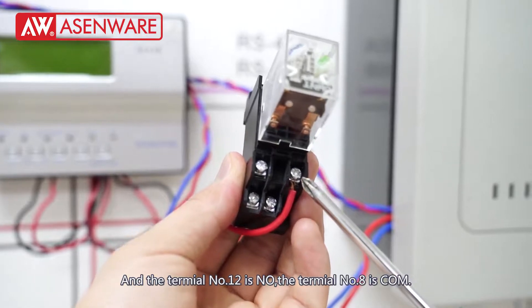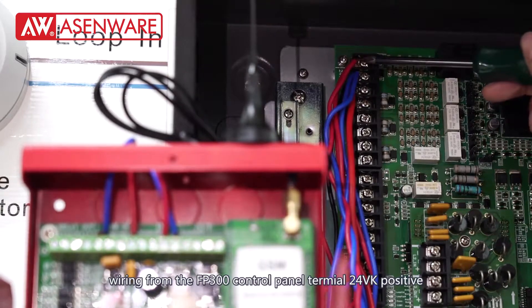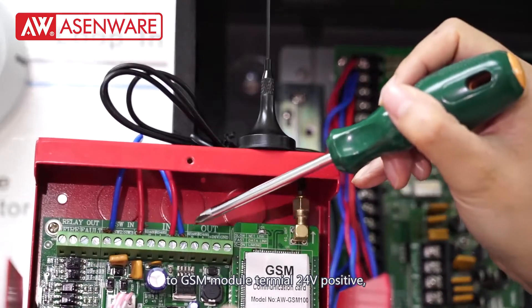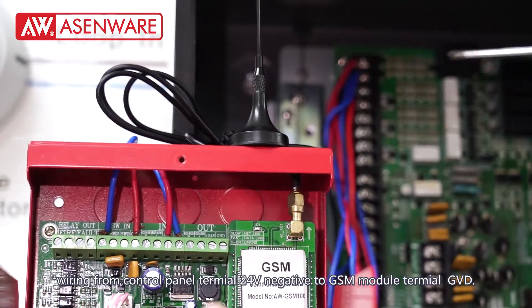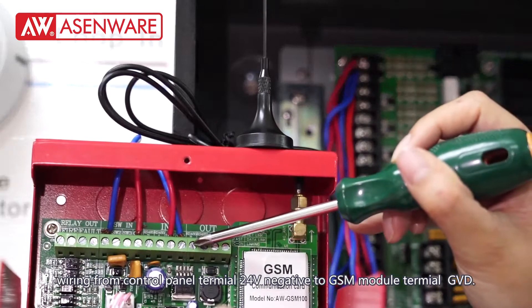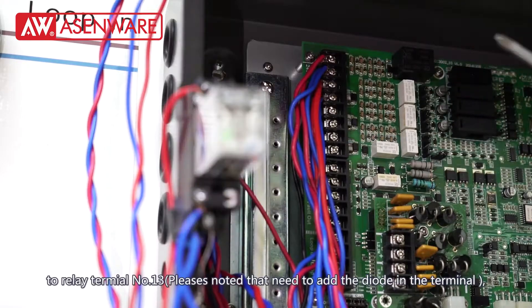Terminal number 8 is COM. Wire from the FP300 control panel terminal 24V positive to GSM module terminal 24 positive, and from the control panel terminal 24 negative to GSM module terminal GVD. Then wire from panel terminal XCR positive to relay terminal number 13.